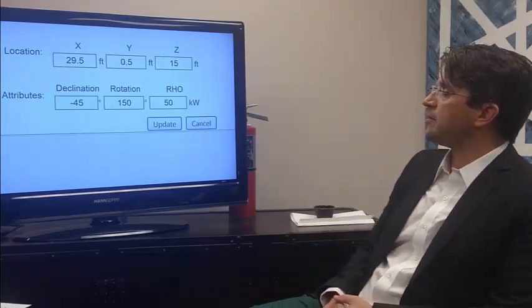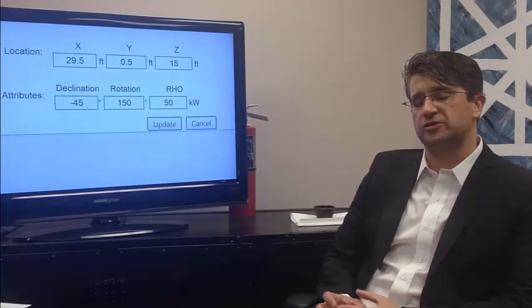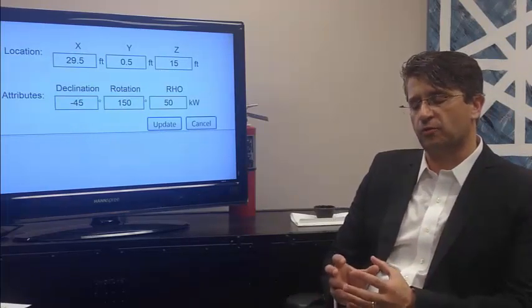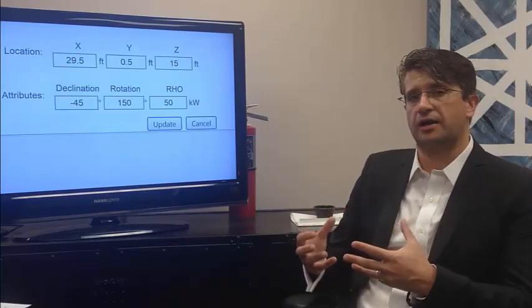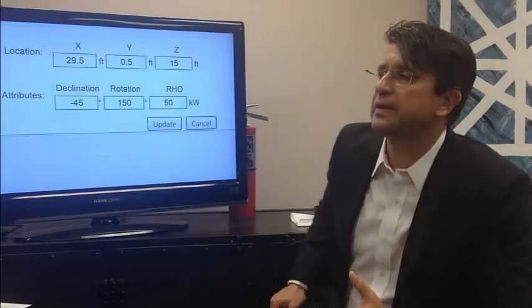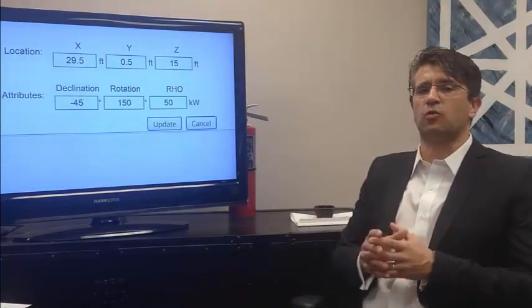A typical number for a high risk area, small fire. So I want to detect a fire when it's small because the risk is high in that zone. It would be given by something like 10 or 12 kilowatts.